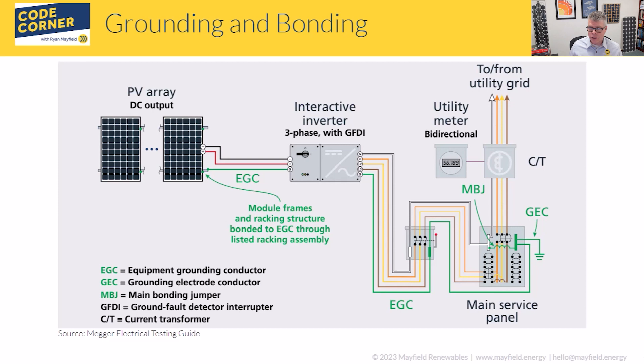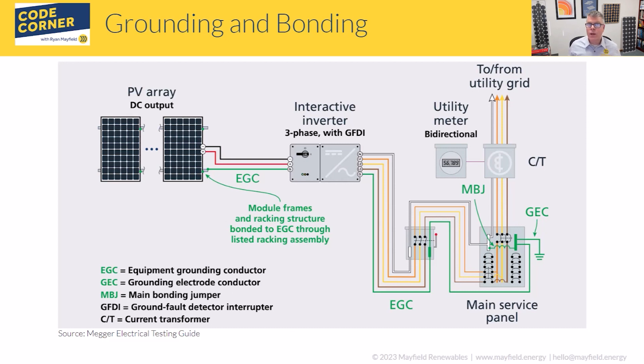Module frames are bonded to the EGC through a listed racking assembly. There are ways of using a non-wire type piece of metal — in PV systems, using the racking system itself as the equipment grounding conductor. You can use listed components to bond the modules to the racking system, making that bond from module frame to racking, then bond the racking back to the rest of the grounding system. The National Electrical Code also allows conduit as an equipment grounding conductor when done properly, but in PV systems we very often use wire-type equipment grounding conductors.